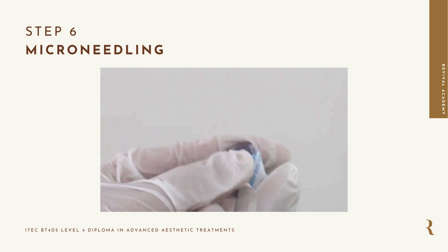Before going ahead with the microneedling treatment, you need to set up your Dermapen that you're going to use. First, remove the packaging from the needle. And place the needle into the Dermapen by screwing it into the pen. Adjust your needle size by rotating the top half of the Dermapen. Select a 0.5 millimeters needle size. And for the intensity of the pen itself, rotate the lower half of the pen and select mode 5. To switch the pen on, select Dermapen from the menu and press on start.